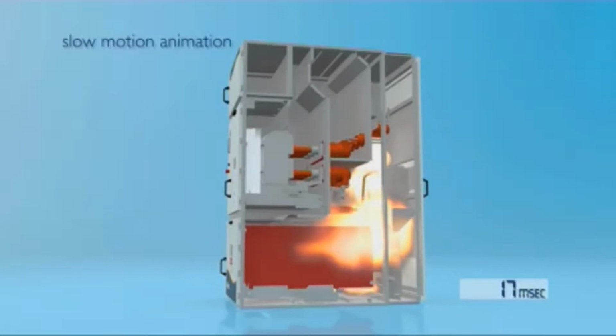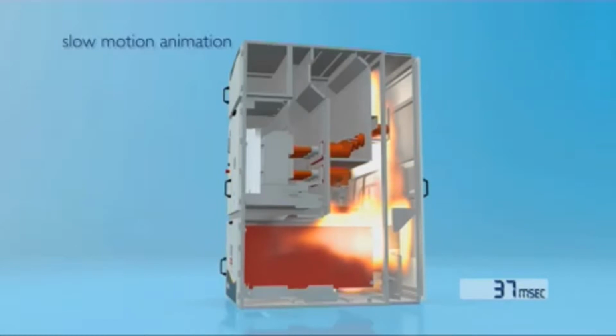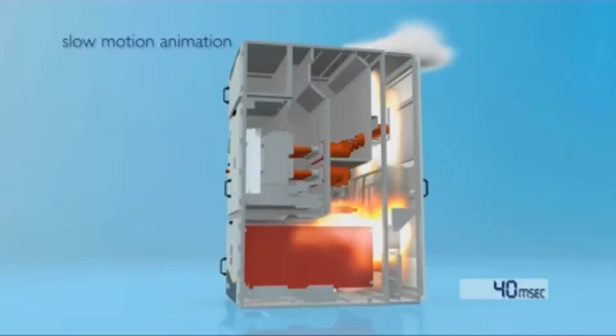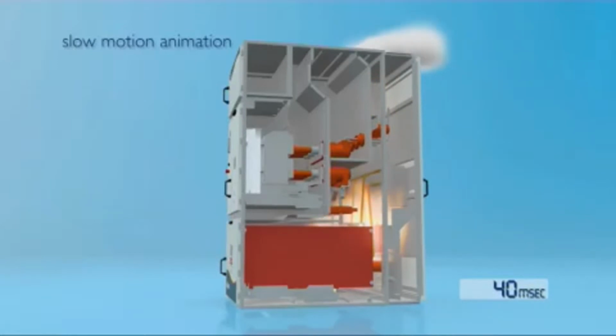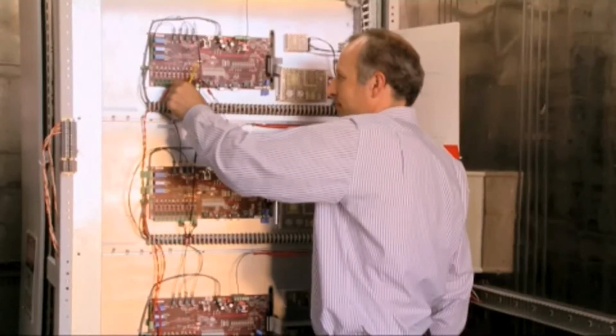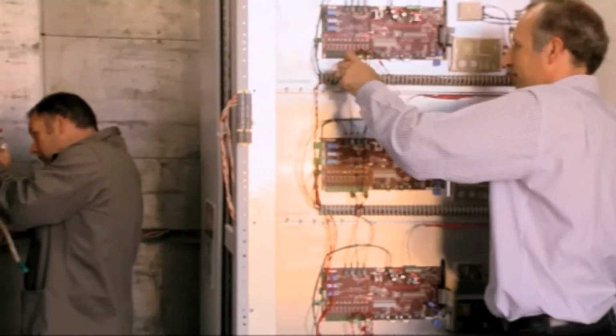The pressure builds to the point where release flaps on the top of the panel open. Heat and gases from the liquefaction of materials is safely released via a ventilation shaft. The operator in front of the panel is unharmed. Your safety is our primary concern.